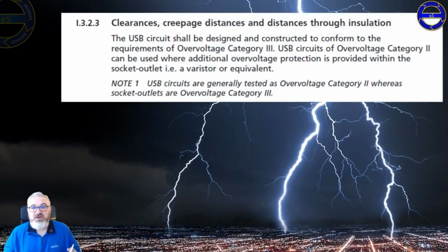So on to the next real issue with USB socket outlets, and that is lightning, overvoltage, transients, voltages that appear that shouldn't necessarily be there. Now in BS 7671, the latest edition, there's a whole section on transients and overvoltage protection, and we seem to now in this edition have rolled out the surge protection devices. So let's get into surge protection devices. Now I'm not going to cover all of the criteria of surge protection devices, because Sparky Ninja's channel does that, and GSH, as well as many other YouTubers.